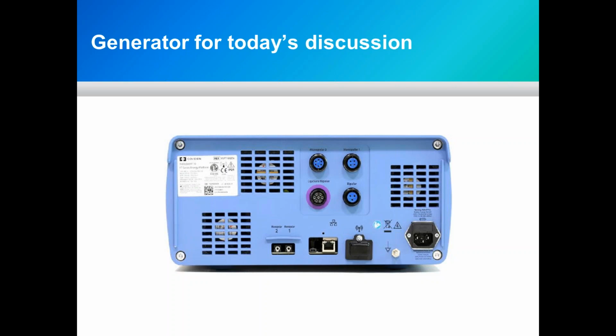And then you have ports for the smoke evacuation, communication ports. So as they continue to implement changes into the FT10, such as networking, the automated OR, if you will, although I think they call that something different, all your ports are located there on the back. One of the other differences that I didn't mention on the preceding slide was the red scanning lights are no longer there. They now utilize an RFID chip in the LigaSure port, so they sense the presence of that instrument differently than they did in past times.